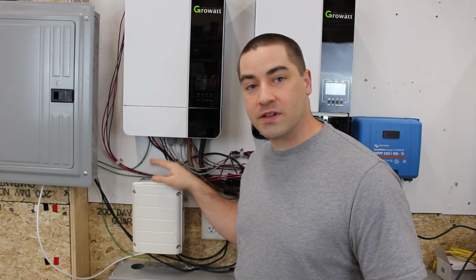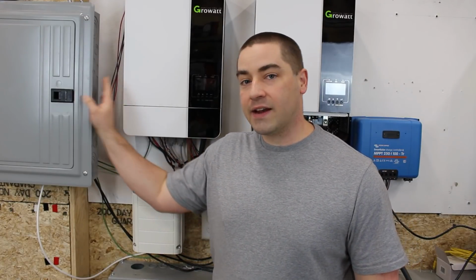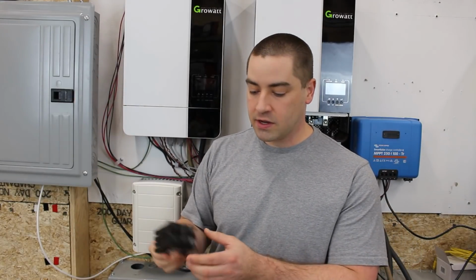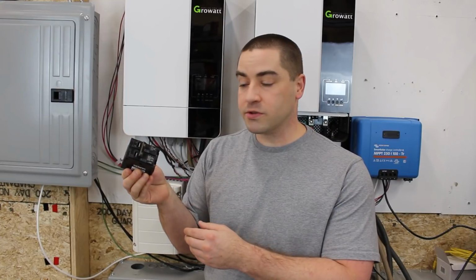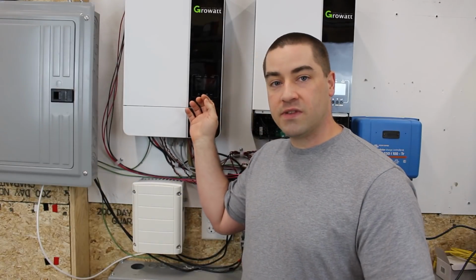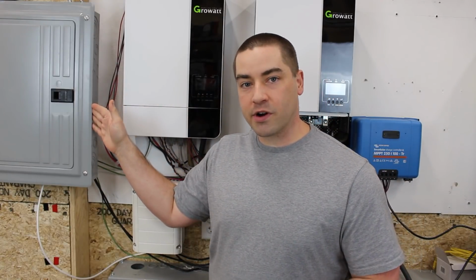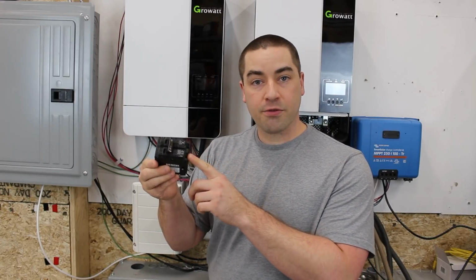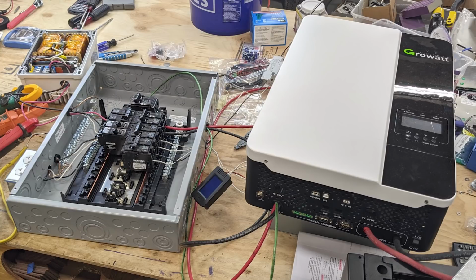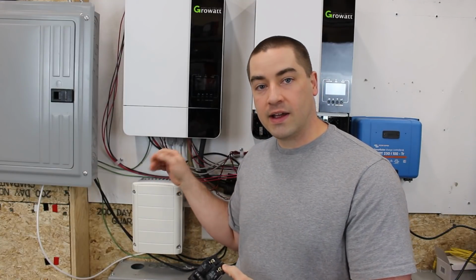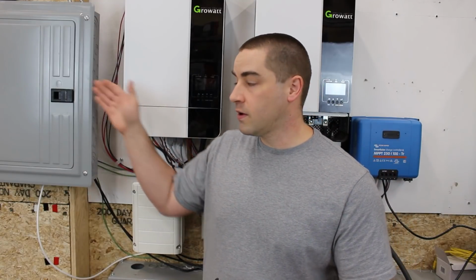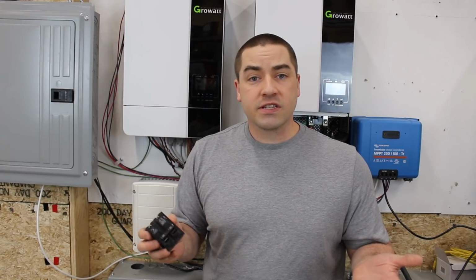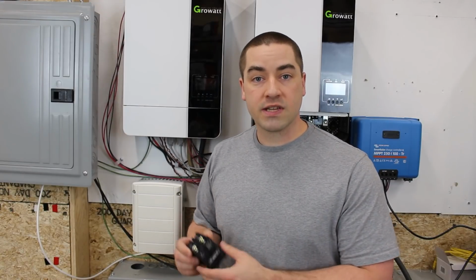When I first wired up this auto transformer, I actually had it feeding off of the circuit breaker box using a standard double pole circuit breaker. So each of these inverters fed into the circuit breaker box, back feeding through one circuit breaker. And then off the same bus bars inside, I had one circuit breaker that fed out to the auto transformer, and then one wire for the neutral feeding back into the neutral bus bar of the panel. Now that just made the most sense to me when I first set it up.